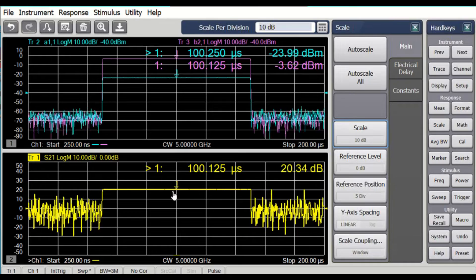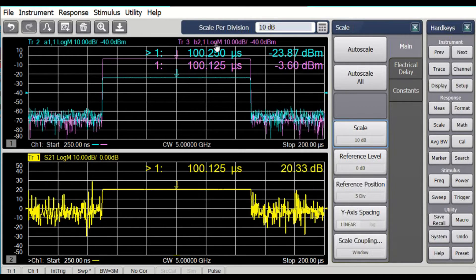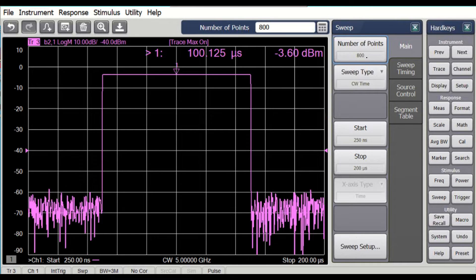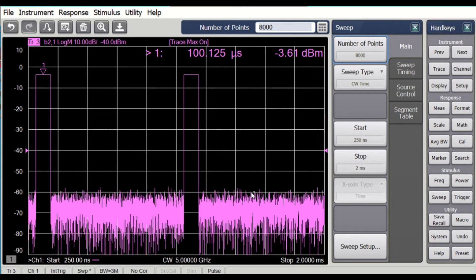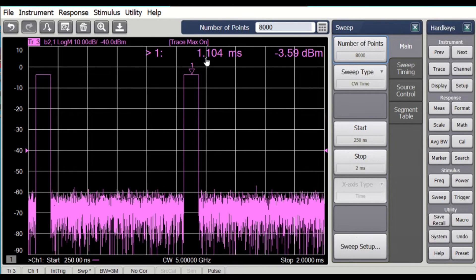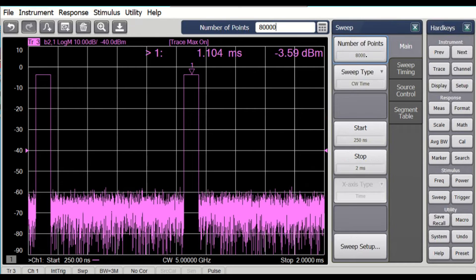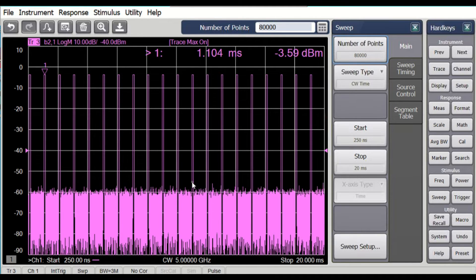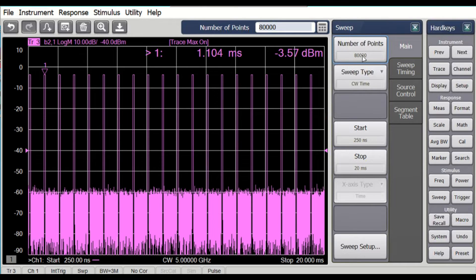That's the simple pulse measurement. Now you might ask: what if I want to see more pulse points or more pulses? Let's take a look at the output pulse. The easiest way to see more pulses is to just set more points. Now it updates the start and stop time. Here's the first pulse — moving the marker over — and here's the second pulse at the millisecond pulse repetition rate. If I go up to 80,000 points, I see a whole pulse train. We're using the PNA receiver as a time-coherent, time-synchronous tuned receiver, so we can look at the pulse width directly by looking at the time on the marker.